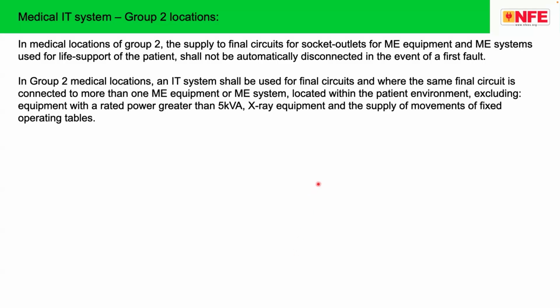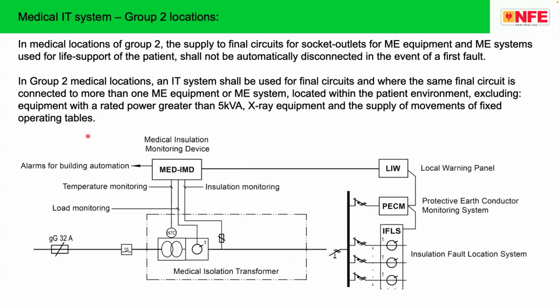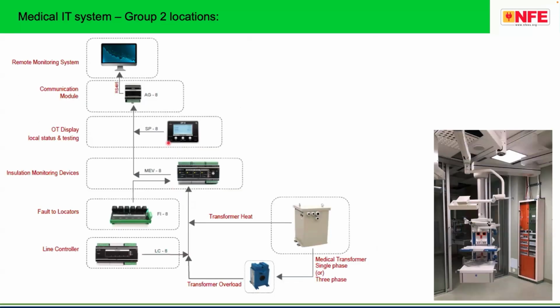In order to avoid such problems, medical IT systems are made mandatory in Group 2 locations in the National Electrical Code of India. These are special electrical supplies, probably from a UPS, but there should be an isolation transformer of maximum 10 kVA capacity, which is feeding multiple small biomedical equipment. This is just an example. There is a transformer, there is a measurement of the temperature and overcurrent of the transformer, insulation monitors are there, fault locators are there, display systems are there, warning systems are there. Finally, it looks like a panel, as shown in this particular picture.